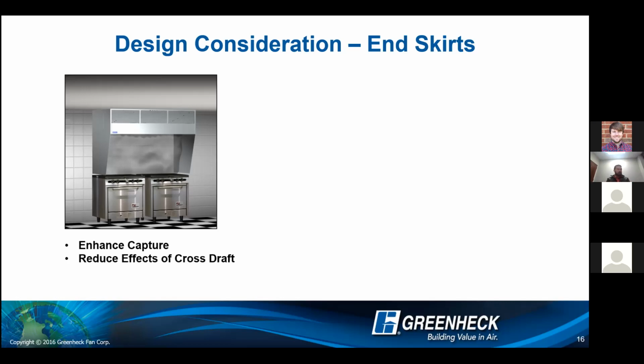If you're working on a project and when it gets to the field you find out that there are cross drafts that you weren't accounting for, know that these end skirts can be added after the fact. It's not always just, hey, I'm not capturing, let's just increase the CFM of the exhaust fan. Look at doing end skirts in order to increase the capture.